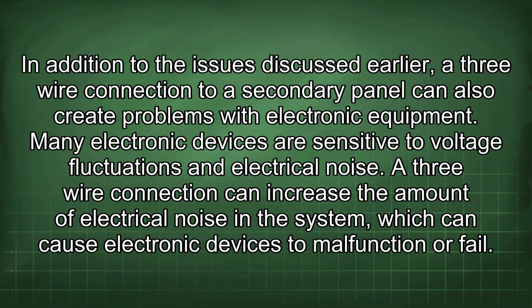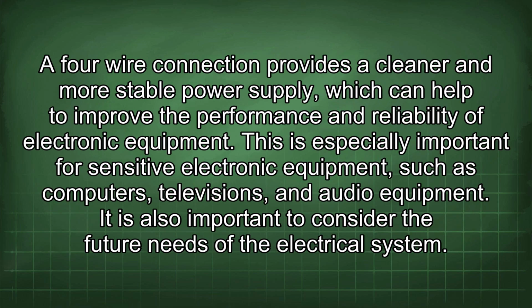In addition to the issues discussed earlier, a 3-wire connection to a secondary panel can also create problems with electronic equipment. Many electronic devices are sensitive to voltage fluctuations and electrical noise. A 3-wire connection can increase the amount of electrical noise in the system, which can cause electronic devices to malfunction or fail. A 4-wire connection provides a cleaner and more stable power supply, which can help to improve the performance and reliability of electronic equipment. This is especially important for sensitive electronic equipment such as computers, televisions, and audio equipment.